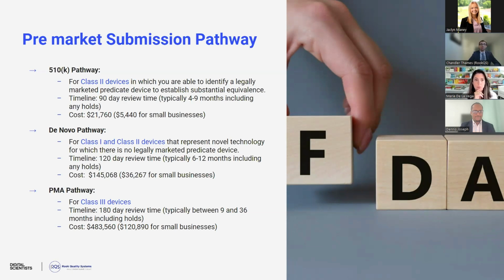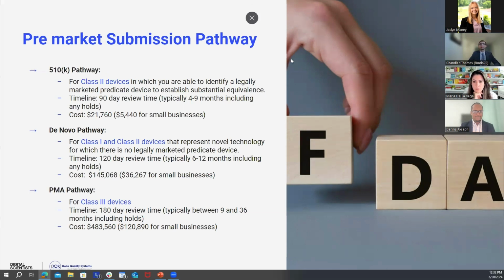But again, this is about 4 or 5 times more expensive than the de novo, and many times more expensive than the 510K pathway. So unless you're absolutely a Class 3 device, it's best to try to pursue a lower device designation. And in some instances, there can be a similar device where the ultimate determining factor between 510K, de novo, and PMA are the indications and the claims that you want to make with the device and exactly how it's used. We can go to the next slide.